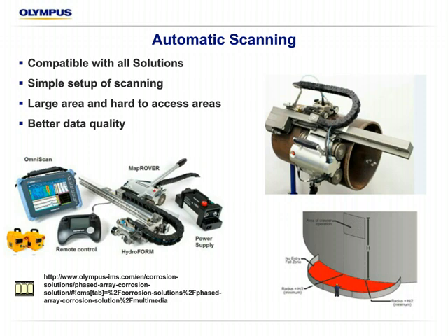So obviously these become a huge benefit for a few reasons. Obviously if it's a hard to reach access area, a steerable, drivable, or some way to get to the area of inspection, especially if you can't scaffold and get a person up there to take more manual readings. But it also has much better data quality when we automate. If we can control the exact speed it's always moving, we can control all those types of things, we're going to get a much better data quality as well.